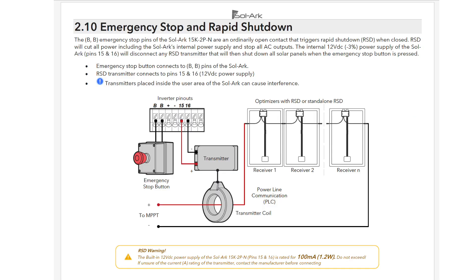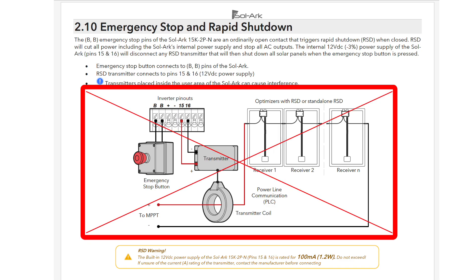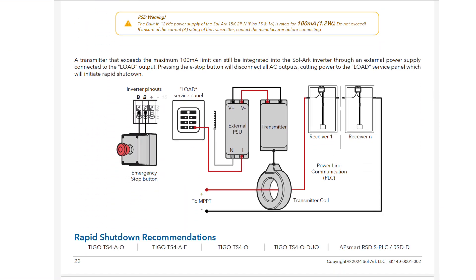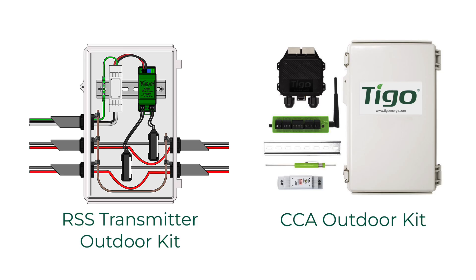Sol-Ark provides two methods for using a rapid shutdown transmitter with their pins. When using Tigo products, you must use the second method shown here and not rely on the Sol-Ark internal 12-volt RS-D pins. Tigo supplies complete kits for both communication products, which are available at your local distributor.